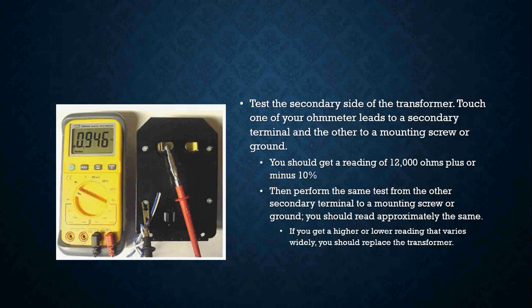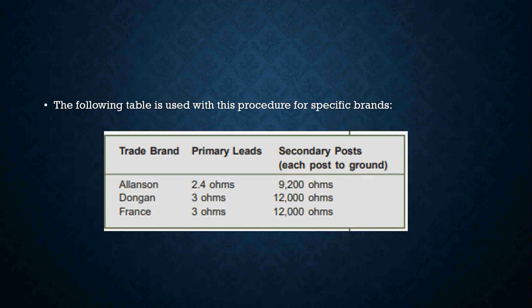Now test the secondary side of the transformer. You touch one of your ohm leads to the secondary terminal and the other to a mounting screw or ground. You should get a reading of about 12,000 ohms plus or minus 10%, and then perform the same test on the other secondary terminal. You should get approximately the same reading. Again, if they're too high or too low or they vary widely, replace the transformer. The following table gives you some guidelines of what you should be reading depending on the type of transformer you're dealing with. For example, for Allanson on your primary side, you might want to see about 2.4 ohms of resistance. On the secondary side, between each post and ground, you're looking at about 9,200 ohms of resistance.